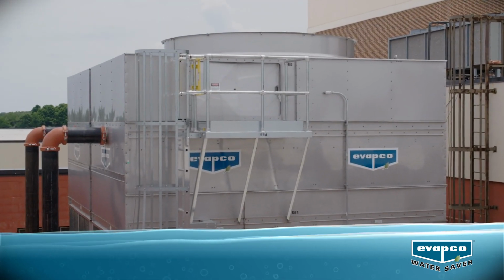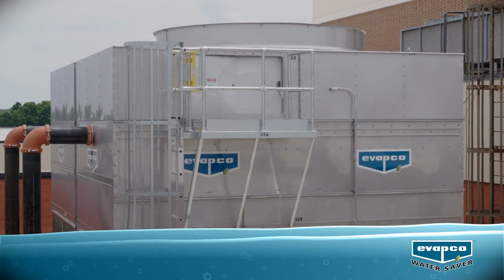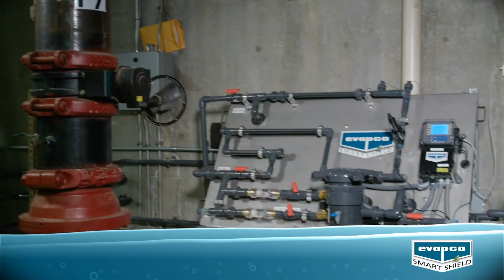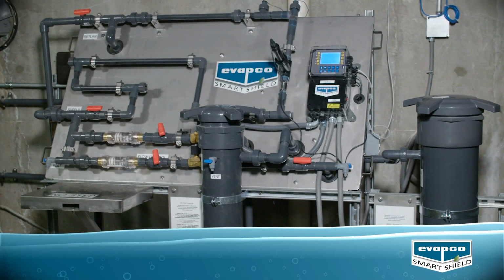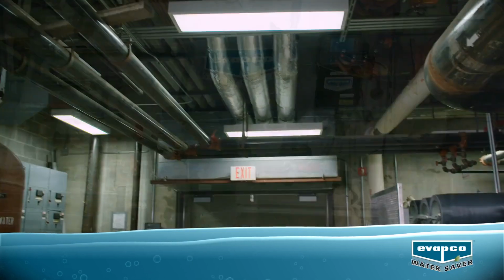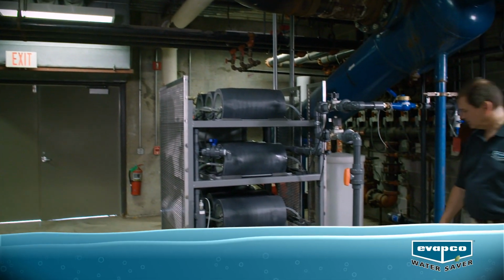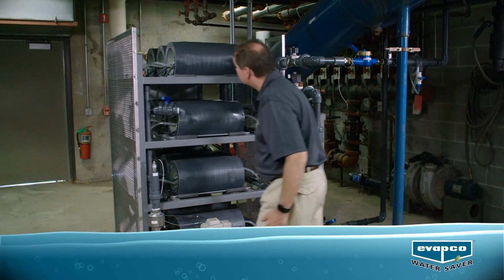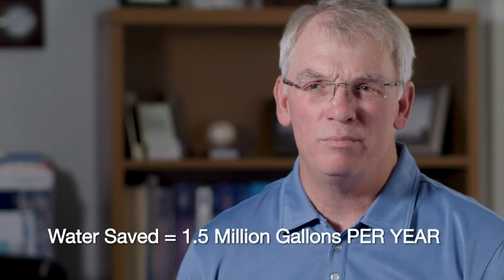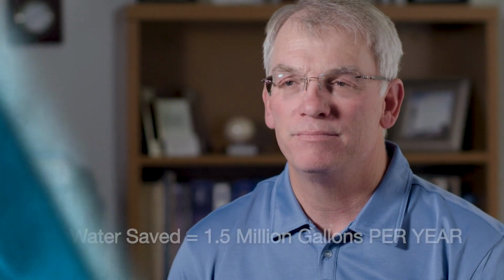We used this opportunity to evaluate our chemical treatment program to determine if we could improve its effectiveness throughout the year. We decided on an EVAPCO Smart Shield solid chemistry system. When we learned about EVAPCO's new water saver technology, we were so impressed that we added it in the project specification along with the Smart Shield system. The Smart Shield and the water saver are performing as advertised. The water saver has improved our makeup water quality about 50%, which has allowed us to double the cycles of concentration to 5. That means we will save about 1.5 million gallons of water per year.